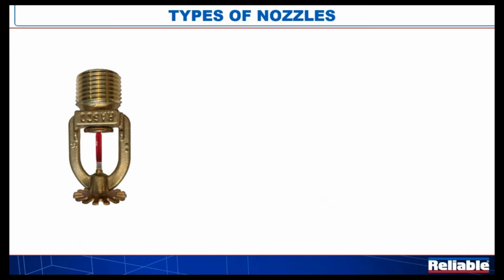On the left is a fire sprinkler. That is just a pendant, 1/2 inch, quick response fire sprinkler, knock the thermal bulb out and take the guts out of it, and it is essentially a low velocity nozzle. And you don't really find that referred to in NFPA 15. It doesn't say, hey, a sprinkler is a low velocity nozzle, but when you do the research, you realize that that's essentially what we're talking about.